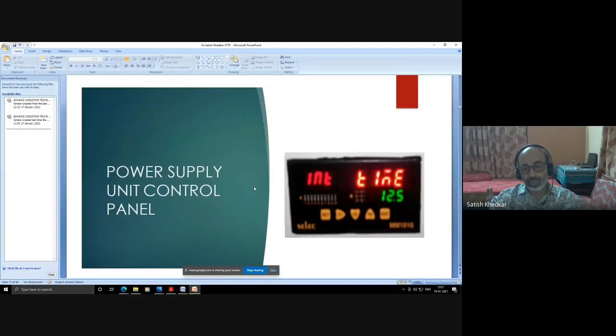So there is the setting for time, and you have to set the time for which the sonication probe has to vibrate. Then there is the control for giving a gap between sonication. That is the start, stop, start option. This we call the pulsed sonication. So if you give a pulse of 2 seconds, 3 seconds between the continuous sonication, then the machine will stop for 3 seconds and again it will restart after 3 seconds. So if you are giving, say, a total time of 10 minutes to the machine, and after 2-2 minute intervals you are giving a pulse of 3 seconds, then after each 2 minutes for 3 seconds the machine will stop and it will restart again.